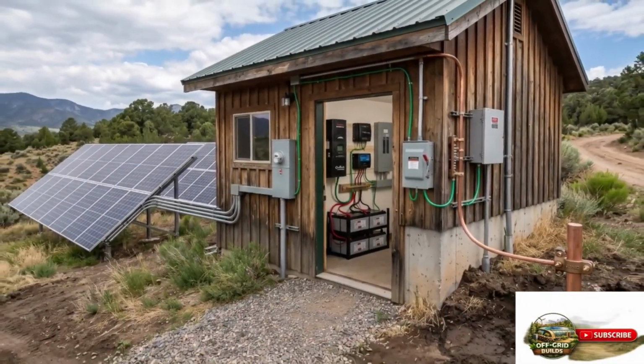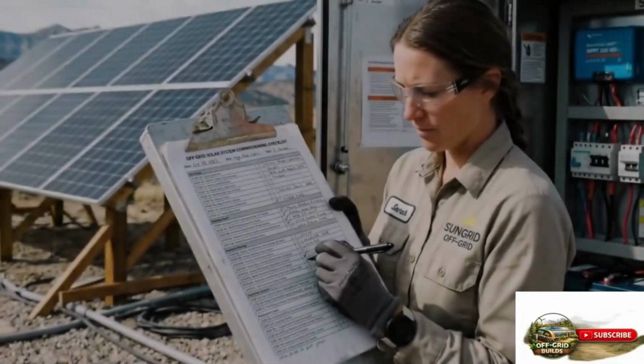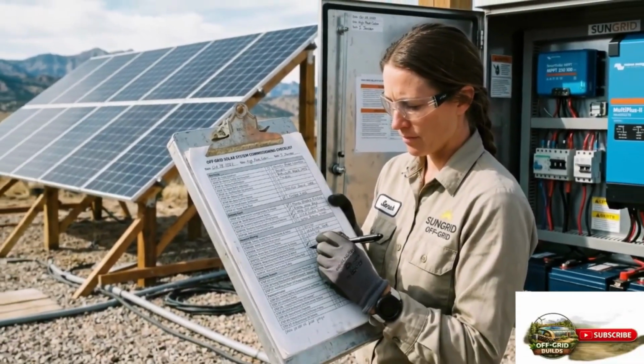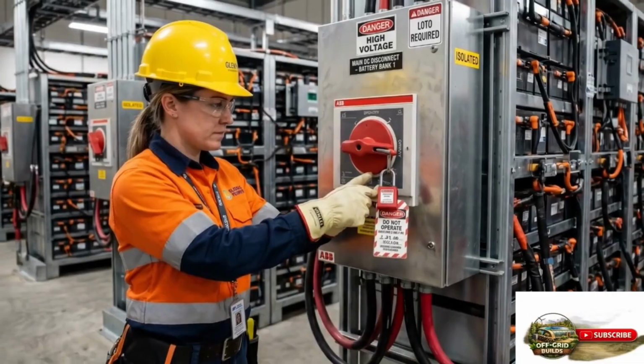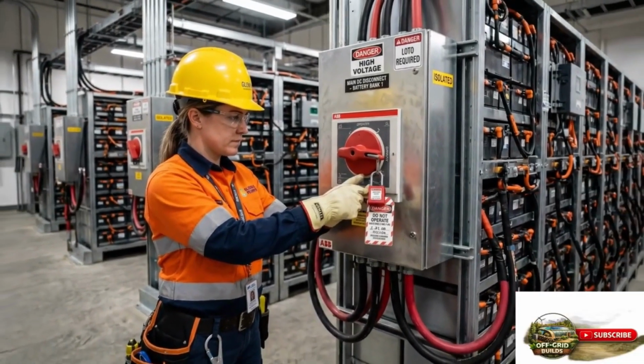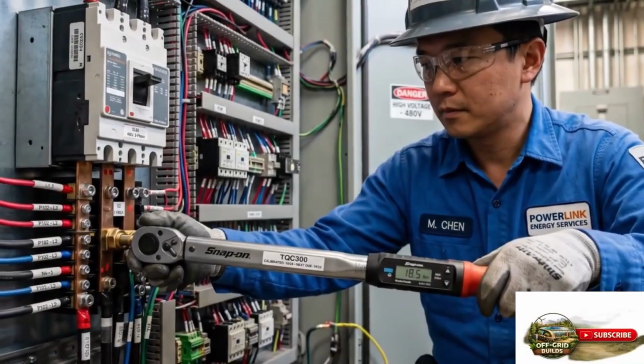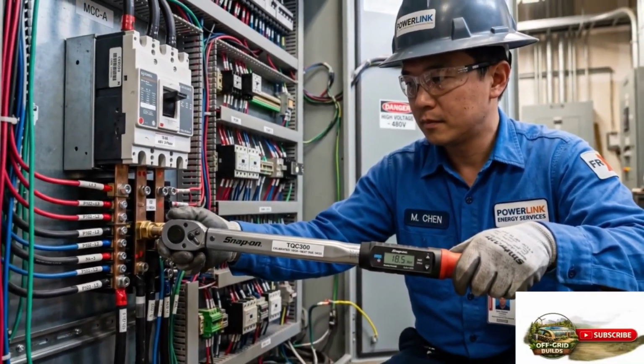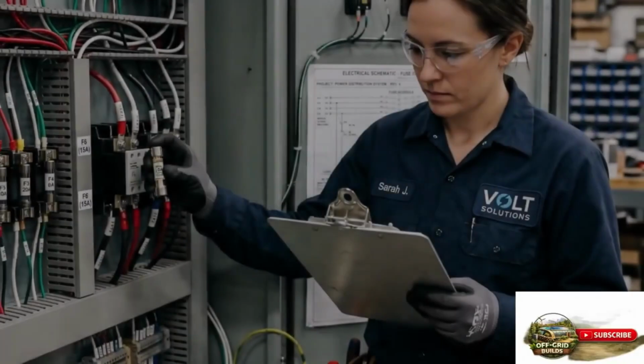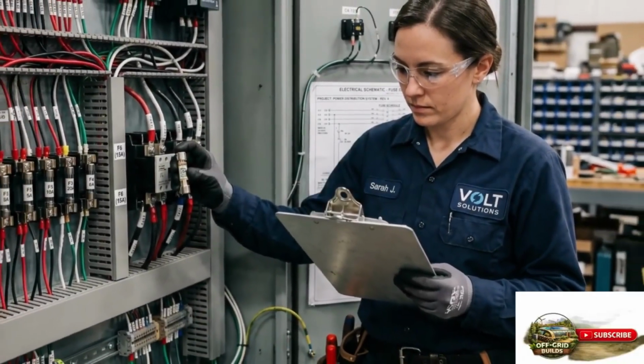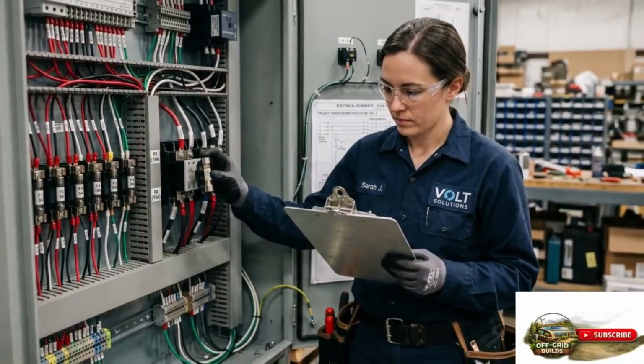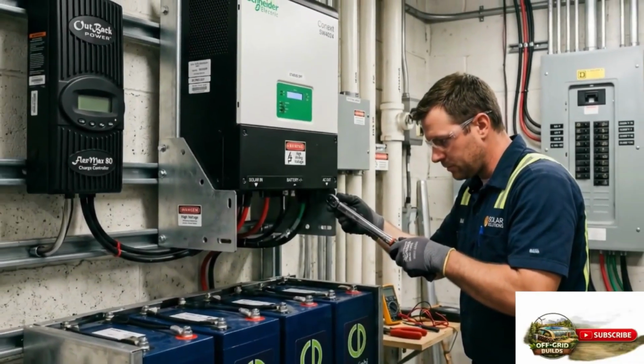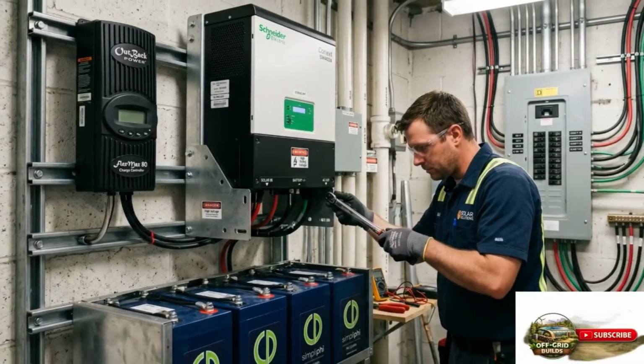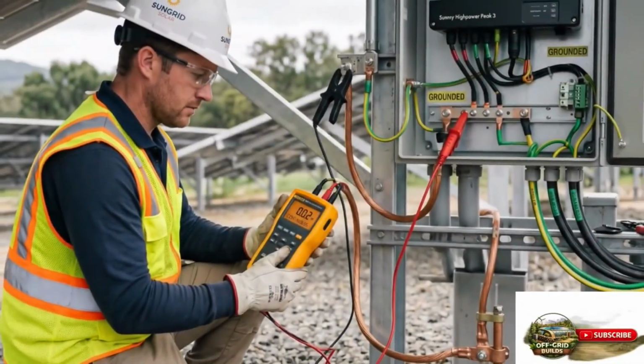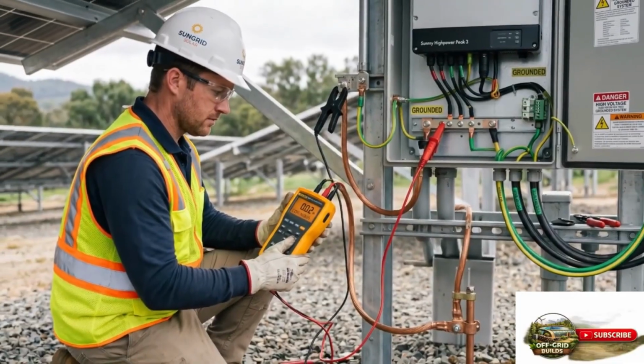Commissioning your system safely. Commissioning is the process of starting up and verifying the operation of a newly installed system before you depend on it for your household's power supply. Rushing the commissioning process or skipping verification steps is the source of many of the most expensive and frustrating problems in off-grid solar installations. The correct commissioning sequence for a large off-grid system begins with the battery bank disconnected and isolated. Verify all wiring connections are secure and correctly terminated. Verify all fuse and breaker ratings match the design specifications.